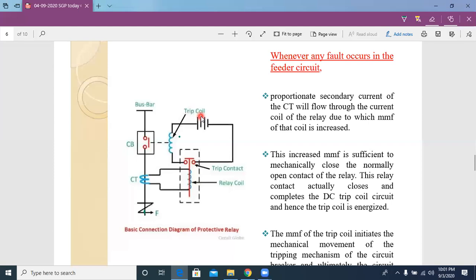One more important thing: relays do not interrupt or eliminate the faults. Relay cannot interrupt or eliminate the faults. It can do only one thing: it can isolate the faulty section from the healthy one. That's all. The main intention of a relay is that it can only isolate the faulty section from the healthy one. It did not do anything from the fault point of view. It only isolates the unhealthy section from the healthy one. That's all. So the same things I write here whenever a fault occurs in a feeder circuit.